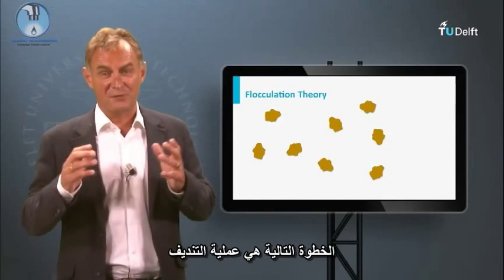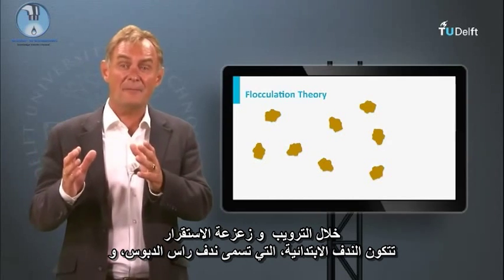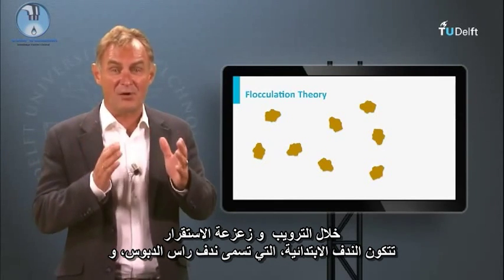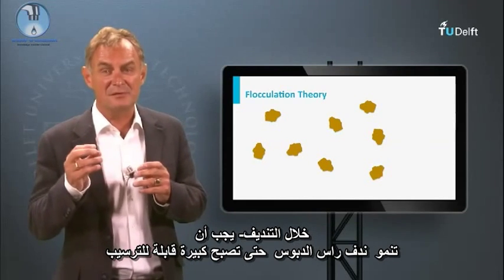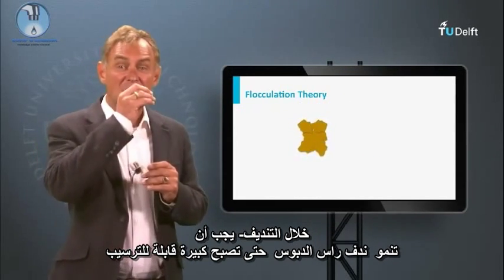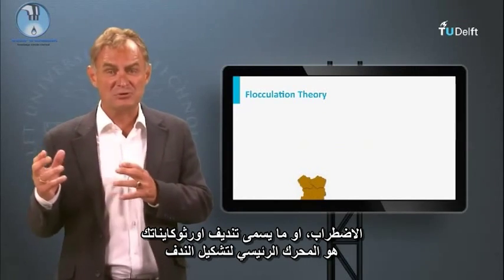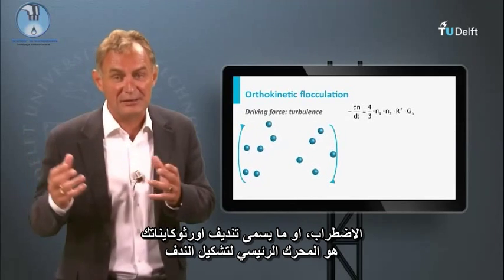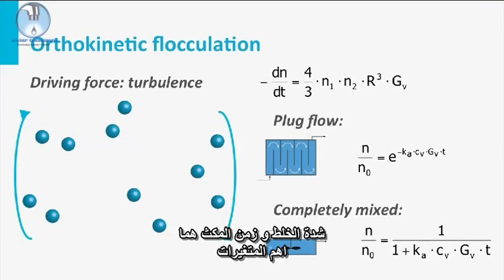The next step is the flocculation process. During coagulation, destabilized elementary flocs — so-called pin flocs — are formed. During flocculation, these pin flocs have to grow into large settleable aggregates. Turbulence, so-called orthokinetic flocculation, is the main driver for floc formation, with mixing intensity and residence time being the most important variables.